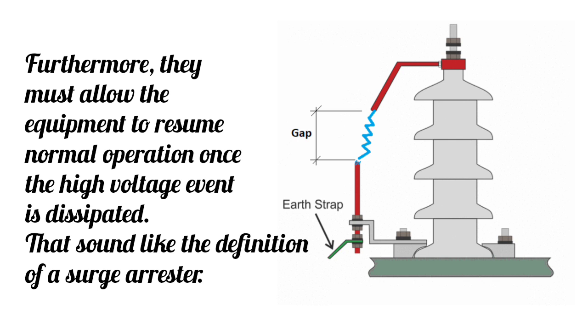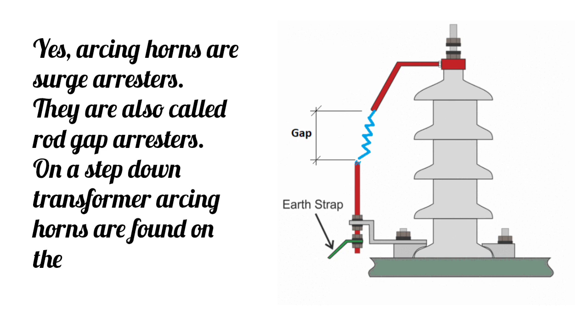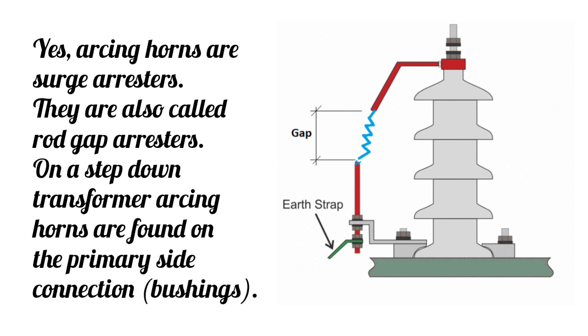That sounds like the definition of a surge arrestor. Yes, Arcing Horns are surge arrestors. They are also called rod gap arrestors. On a step-down transformer, Arcing Horns are found on the primary side connection bushings.